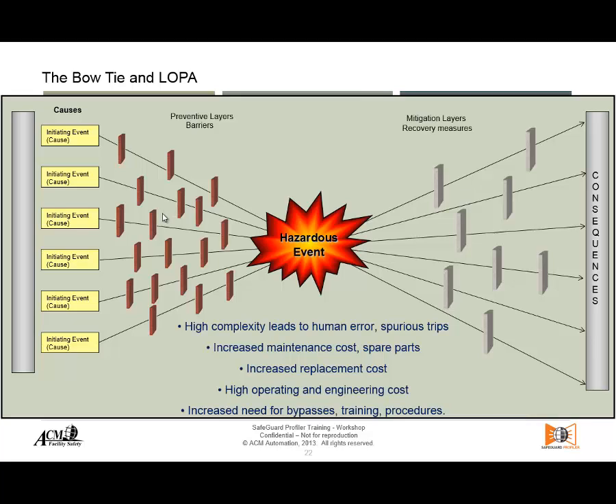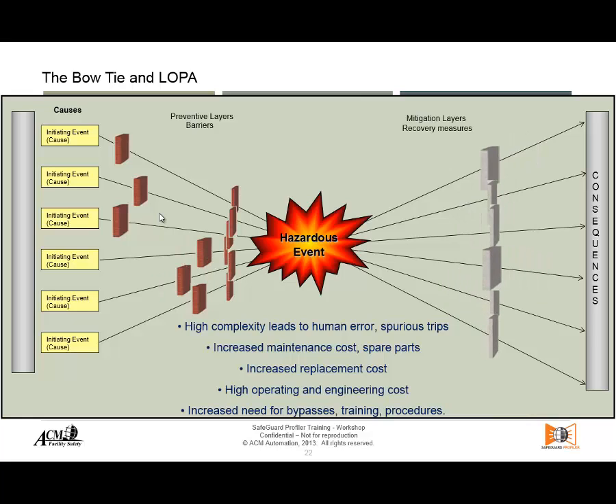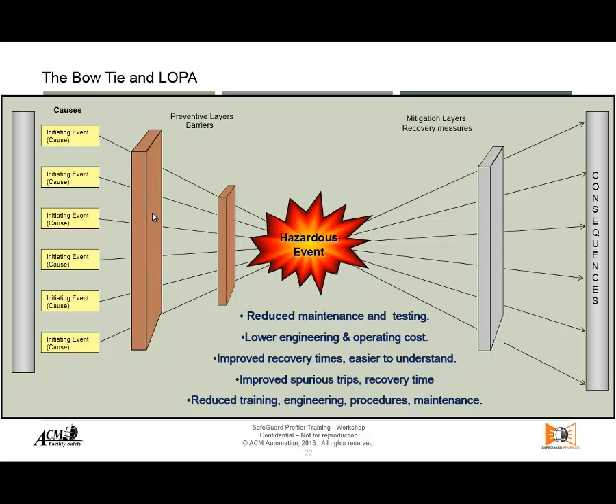Safeguard Profiler allows us to do that when we perform layer protection analysis. We can take all those safeguards that are not needed or can be simplified and maybe keep only two or three that provide the same amount of risk reduction but with less complexity and less maintenance. Instead of having 10 safeguards, we'll have two. Our operating and engineering cost goes down, and we reduce maintenance, testing, and engineering effort, while having easier-to-understand processes and systems.